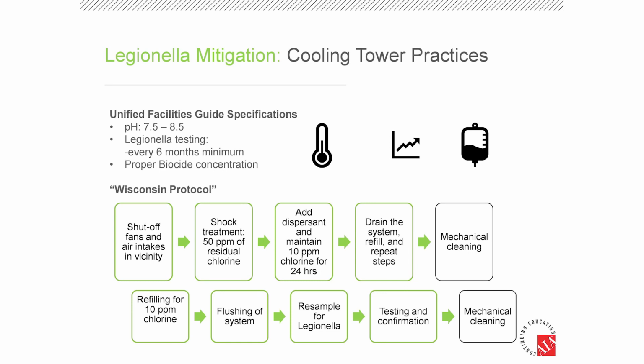So for cooling towers, here's some protocol. The federal guide specs talk about maintaining pH of 7.5 to 8.5, just to make sure it's not too acidic or too basic. Legionella testing every 6 months is a minimum. So by maintaining the right biocide content, feeding them, and making sure the equipment that feeds the biocides is maintained and has the right levels.